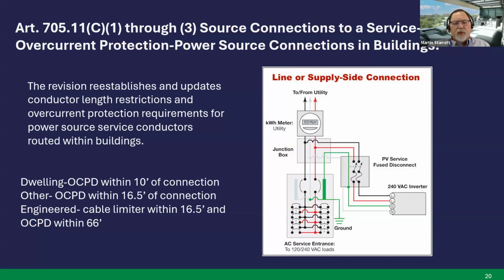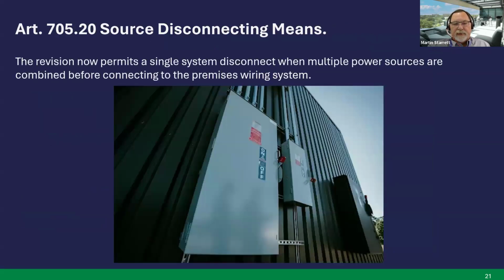So in dwelling units, you have to have an overcurrent protection device within 10 feet of the connection. Other than dwellings, an overcurrent protective device has to be within 16.5 feet of a connection. And then if it's an engineered system with a cable limiter installed, it can be within 16.5 feet, and with an overcurrent protective device within 66 feet. Next slide.